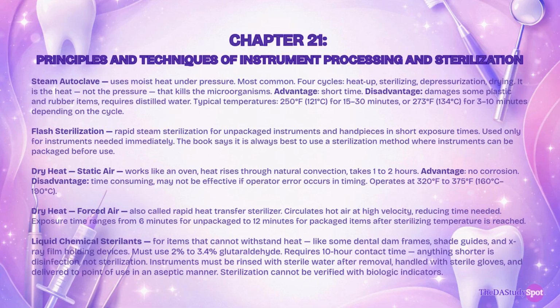Typical temperatures are 250 degrees Fahrenheit for 15 to 30 minutes or 273 degrees Fahrenheit for 3 to 10 minutes, depending on the cycle. Then there's flash sterilization, which typically happens in an office that is very busy with multiple providers. This is rapid steam sterilization for unpackaged instruments and handpieces in short exposure time, used only for instruments needed immediately. For example, the schedule is full, you just use your last clean restorative pack and your next crown patient walks in. But of course, the best method is sterilization where instruments can be packaged before use.